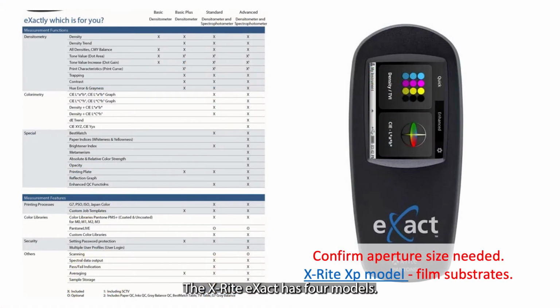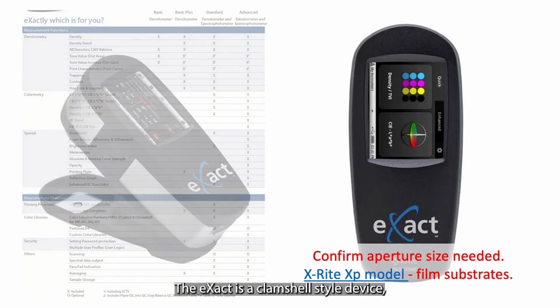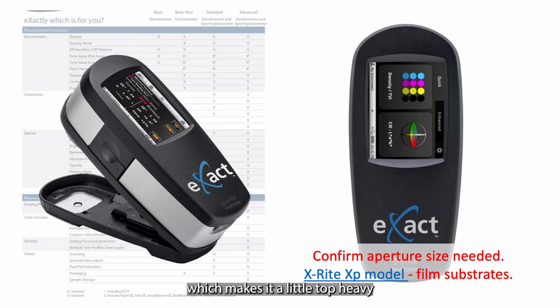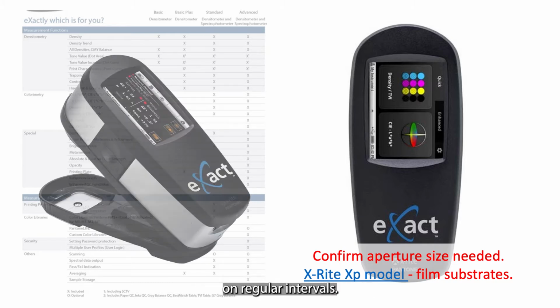The XRite Exact has 4 models. The first 2, the Basic and the Basic Plus, are only densitometers. The standard and advanced models collect spectral information. The advanced model has additional measurement features such as measuring opacity. The Exact is a clamshell-style device, which makes it a little top-heavy when in the unlocked mode. However, it has a handy built-in calibration tile and will force calibration on regular intervals.